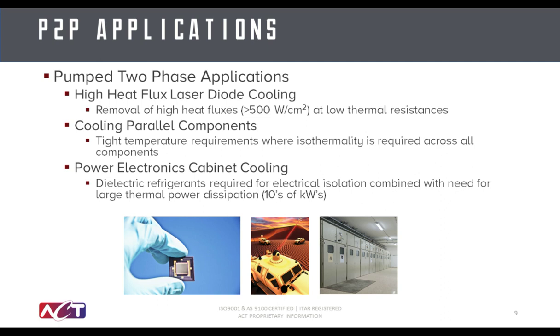As alluded to earlier, some applications that benefit from pumped two-phase cooling mostly revolve around high heat flux applications. Laser diode cooling is a good example because you often have very high heat loads in very small packages. These heat fluxes can be greater than 500 watts per centimeter squared, and they typically require quite cool temperatures, needing low thermal resistance. You can also cool parallel components with a pumped two-phase system by incorporating flow restrictions at the entrance to multiple cold plates. All of the cold plates can then be operated at the same temperature, improving the isothermality across the system.